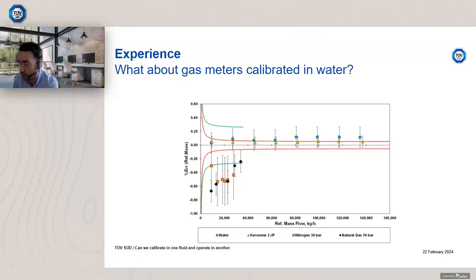The point here is, what would you choose? How would you calibrate this device? Can you calibrate it in liquid? My recommendation, and it's not absolute, it certainly depends on your application, what your uncertainty is, what device you're using, the size of the device, and the availability of calibration fluids. One potential option is you do partly match mass flow. So for example, you pick 2 or 3 flow rates that match the same mass flow, and then you also match meter turndown. So you potentially match velocity, or you match the turndown of the liquid flow range with the turndown from the gas flow range.